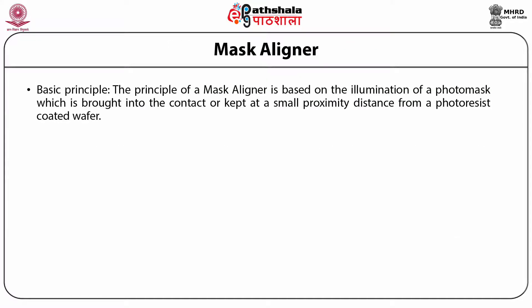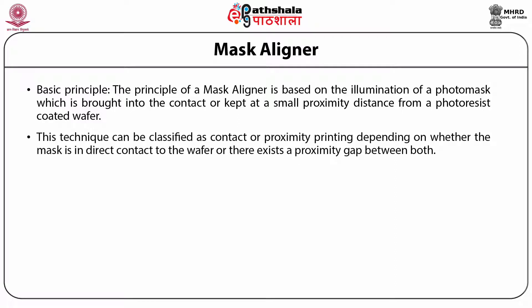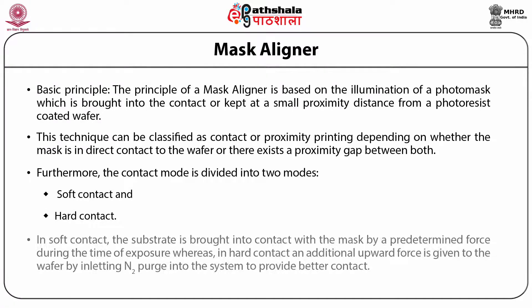The principle of the mask aligner is based on the illumination of a photomask which is brought into contact or kept at a small proximity distance from a photoresist-coated wafer. This technique can be classified as contact or proximity printing depending on whether the mask is in direct contact with the wafer or there exists a proximity gap between both. The contact mode is divided into two modes: soft contact and hard contact. In soft contact, the substrate is brought into contact with the mask by a predetermined force during exposure, whereas in hard contact an additional upward force is given to the wafer by introducing a nitrogen purge into the system to provide better contact.